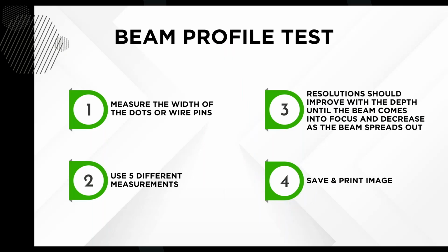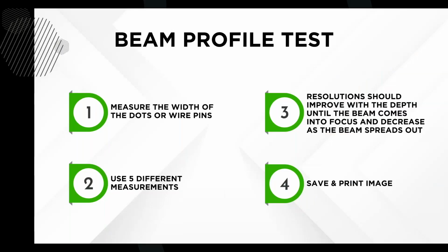So same thing, you would want to be still in the same preset that you were in. Just to confirm, we're under vascular and the carotid preset. So this being a 12 megahertz probe, the beam form is going to come in closer to the top of the image. So you go here, we would measure. All right. I don't think we have enough to measure 5 dots here, but you'd measure each dot.